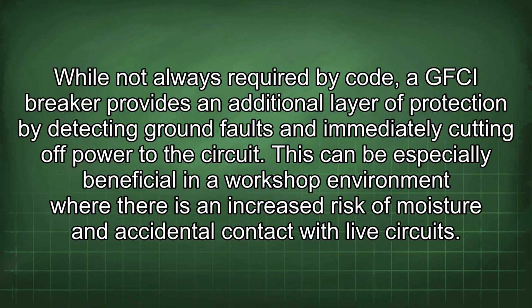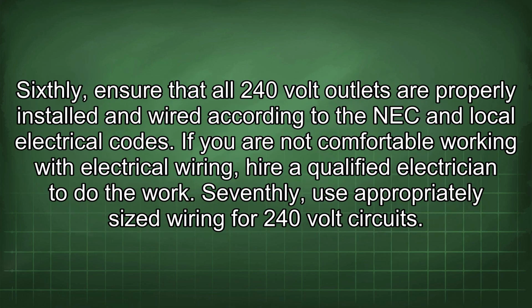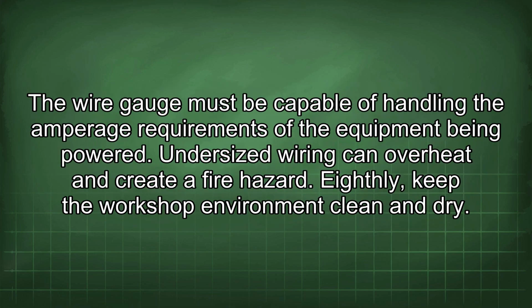with live circuits. Sixthly, ensure that all 240-volt outlets are properly installed and wired according to the NEC and local electrical codes. If you are not comfortable working with electrical wiring, hire a qualified electrician to do the work. Seventhly, use appropriately sized wiring for 240-volt circuits. The wire gauge must be capable of handling the amperage requirements of the equipment being powered. Undersized wiring can overheat and create a fire hazard.